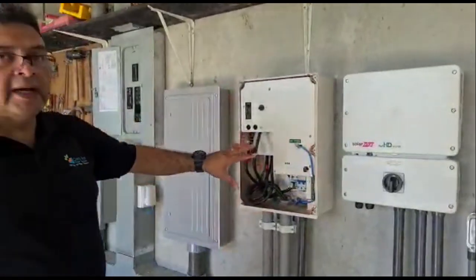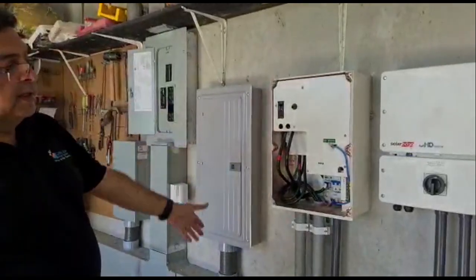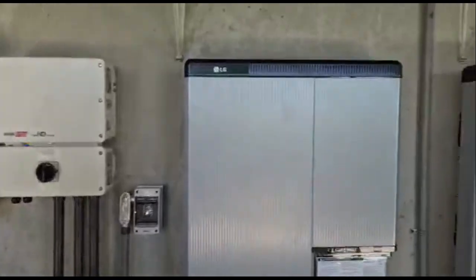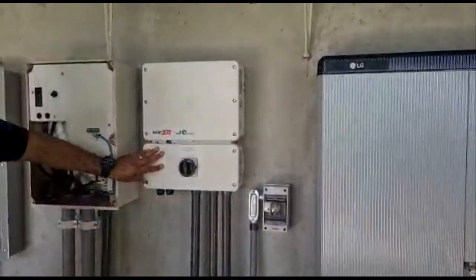At this point, all the power of the house is running through the interface and being fed into the main breaker box. Then we have the two batteries — the main battery and the secondary pack battery — running power through this breaker box and into the inverter.